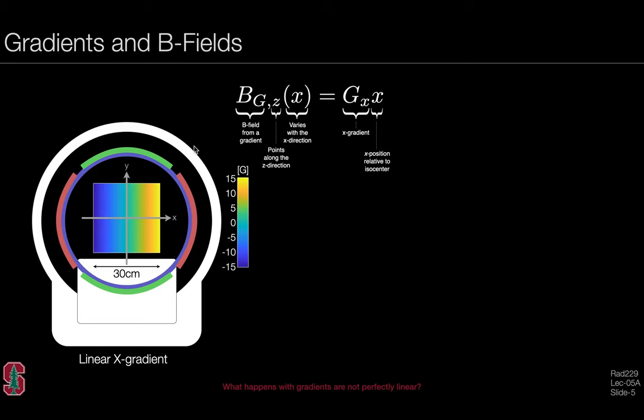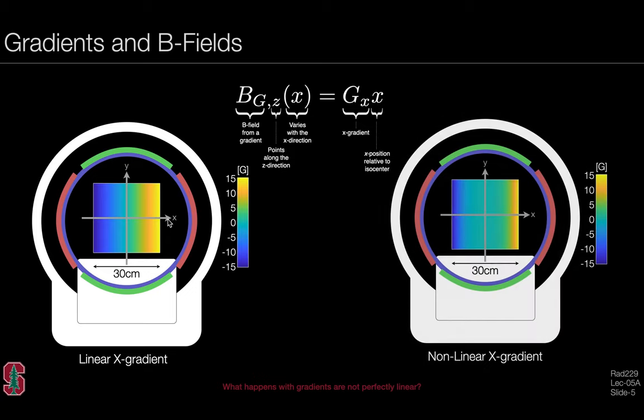In the case of a linear x gradient, we might expect the B field generated from the gradient to decrease on the left-hand side and increase on the right-hand side in a linear fashion. Now, in the presence of nonlinear gradients, the spatial distribution of B field will be a nonlinear function of space, and this will create several problems, especially for image encoding.